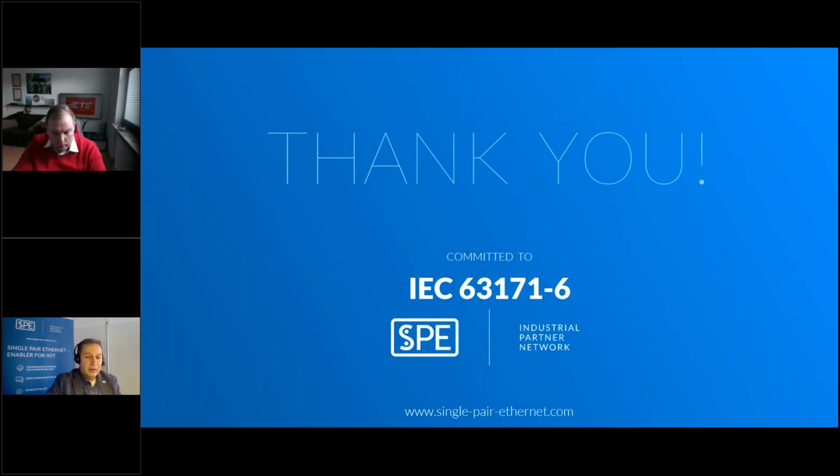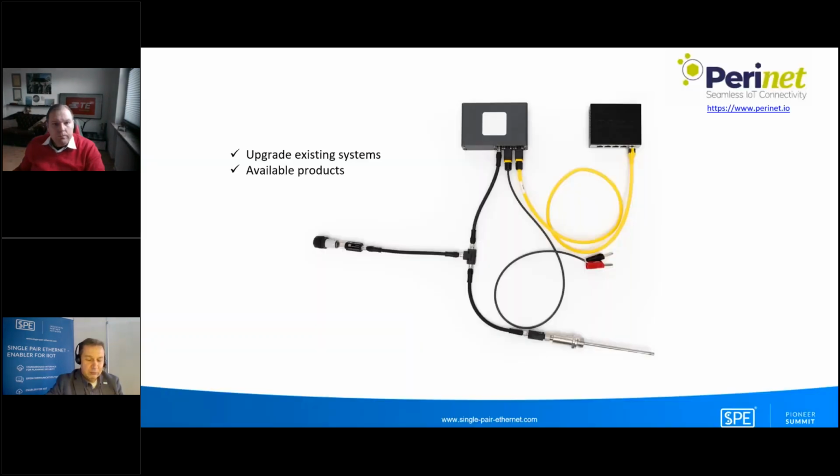Inside your sensors or inside the switches, you also need additional space, especially as you showed these very small M8 hybrid based devices from Perinet. You see they are very tiny. There's no space for additional filters and so on. And especially if you transmit more power, the filters become a space requirement, bigger components. And what you also pointed out very well, the majority of sensors and actuators are at a short distance, below 20 meters or something like this. And on the other side, if you compare PoDL with the hybrid solution, of course there is a little bit higher cost for the cable, but especially for short distances it's not a big issue. And we go with all the systems more or less into the real harsh environment.